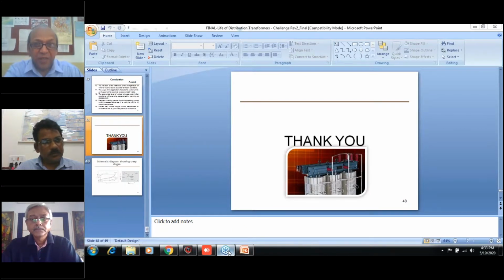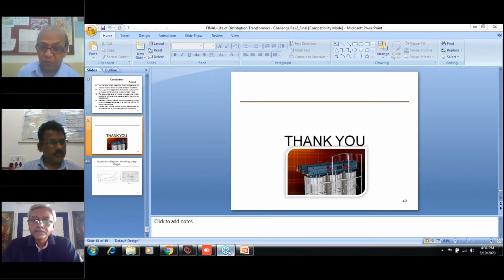They are also causing failure, mostly appearing as termination failure, which may show up after 1, 2, 3 years, or a longer period. It is a reliability problem, but it must be studied and looked into. Harmonics should not only be looked at from the loss point of view, but also from the mechanical vibration point of view. That is important if you want a reliable transformer lasting 10 or 20 years. I don't want to overlook this side and then find my transformer failing. We require studies in locations where harmonics is more, to understand what is going to happen.